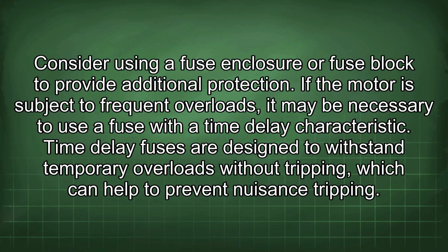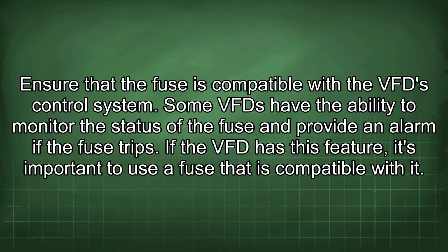If the motor is subject to frequent overloads, it may be necessary to use a fuse with a time delay characteristic. Time delay fuses are designed to withstand temporary overloads without tripping, which can help to prevent nuisance tripping. Ensure that the fuse is compatible with the VFD control system. Some VFDs have the ability to monitor the status of the fuse and provide an alarm if the fuse trips. If the VFD has this feature, it's important to use a fuse that is compatible with it.